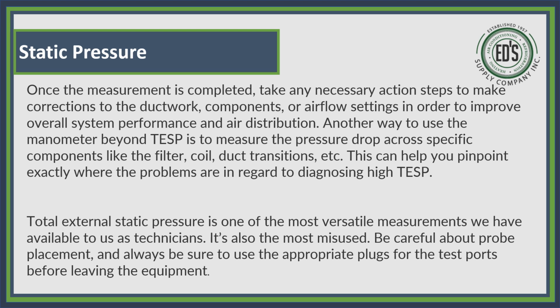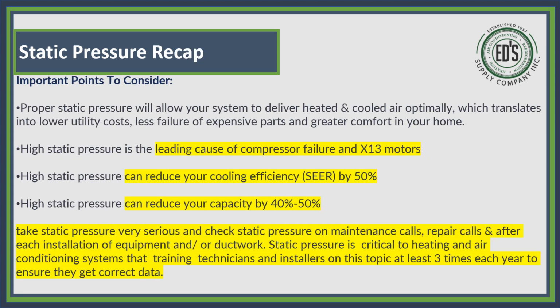Make sure you tape your holes up. And we'll go over to kind of show you things you can do. Like you can determine if a coil is dirty without having to take the sides of it off and actually crawl in there and look up in it, or rip open the flex and stick your head up in there to test that, and then worry about trying to get the flex taped all back up. You can do that with static pressure plugs.